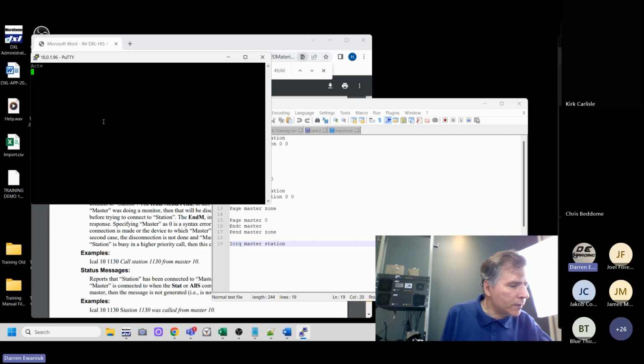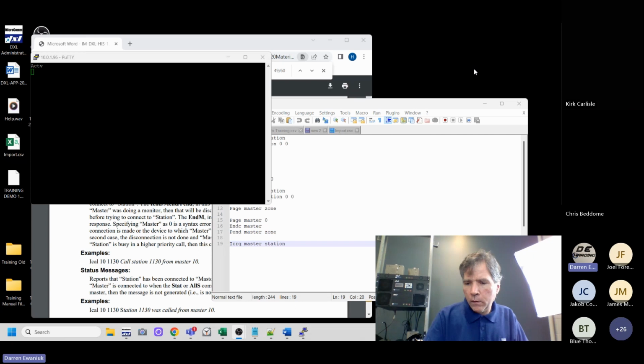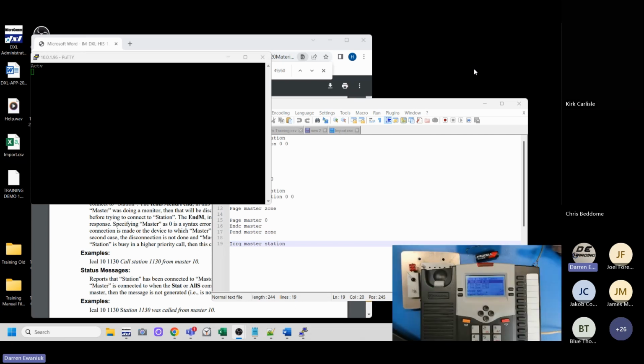Now you're going to see a bunch of messages. If you look at my master screen, I've set my master so that if there are any intercom faults, it's going to report on the master. So I have F and then 102. I don't have intercom station 102 connected, so it's telling me 102 has a wiring fault, which is good. That's what it is. 103 isn't connected, so I'm hitting the next answer button to clear that off, just like hitting acknowledge on the front panel of the DCC. So I have all these intercoms that are not connected.